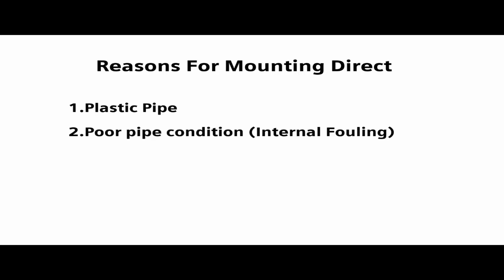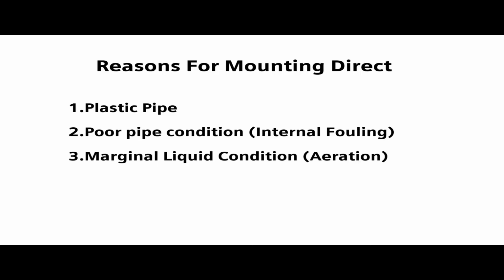So what are the reasons why you would mount direct? Well, the most common is when you're installing on plastic pipes. Because plastic pipes do not conduct a pipe wall signal or lamb wave, they require the installation of the sensors in direct mount. Also, when a pipe is in poor condition, such as a pipe with internal fouling or a very old cast iron pipe which is not a very good sonic conductor, you'll get better results with the sensors mounted in direct mount. And of course, if the liquid conditions are marginal, conditions such as high aeration or high solids content in a slurry, for example, may cause a loss of sonic energy, which can be overcome by going into direct mount. There are also some other application conditions that would be a cause for direct mounting. Our tech support group can be helpful in guiding you in those situations. So without further ado, let's move forward into actually performing a direct mount installation on an actual pipe.